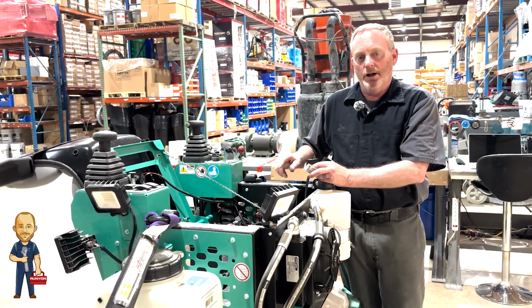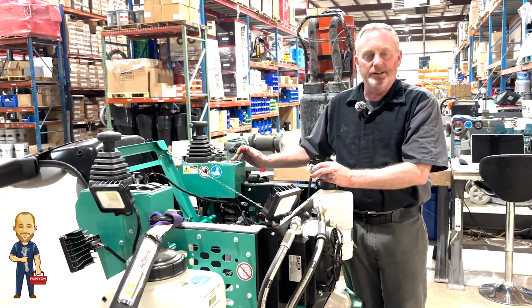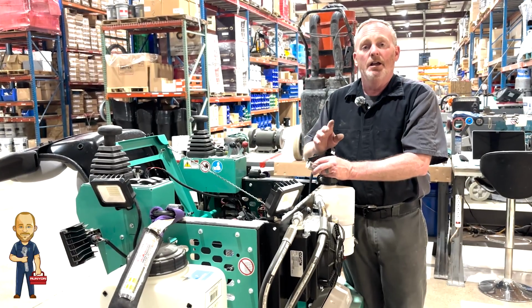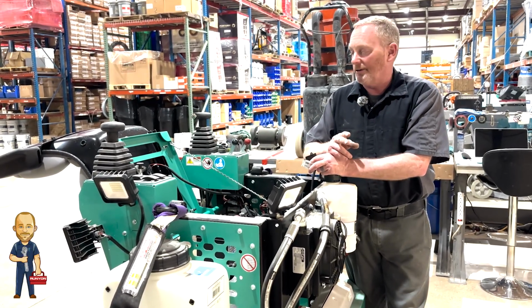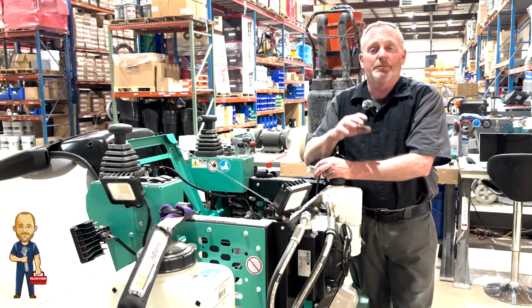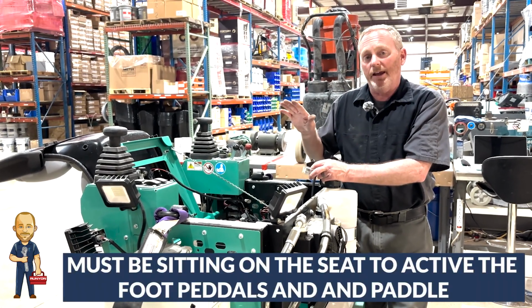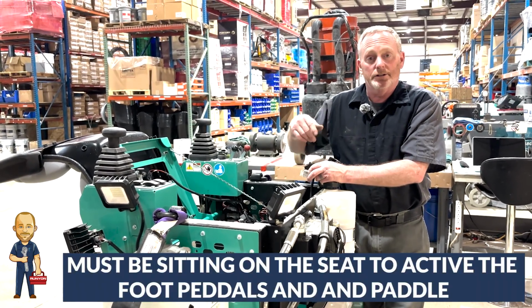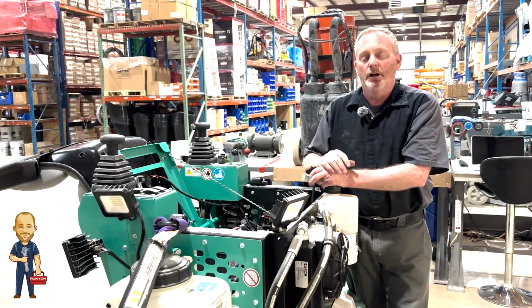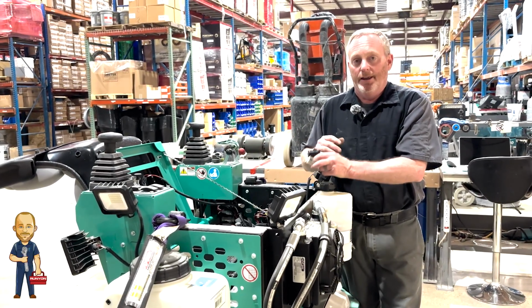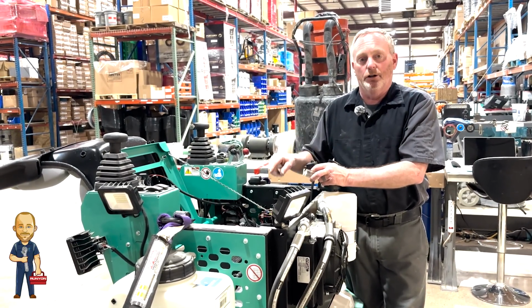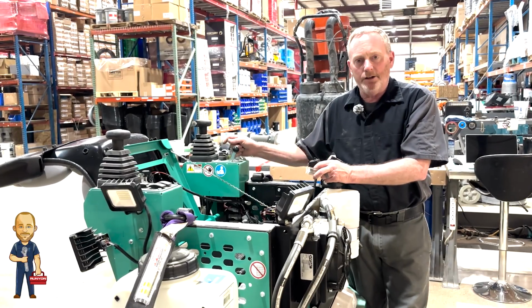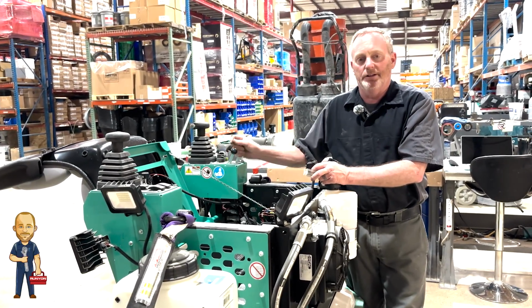So this transformer, the amplifier, and this potentiometer all work in circuit. But two other things work in circuit with it: the seat switch, you have to be sitting on the seat, and then you activate your foot pedal to activate your paddles. Once those two are activated, the transformer voltage can go to the amplifier, and you can use your potentiometer, your speed level.